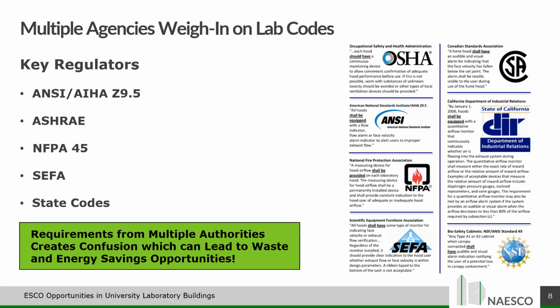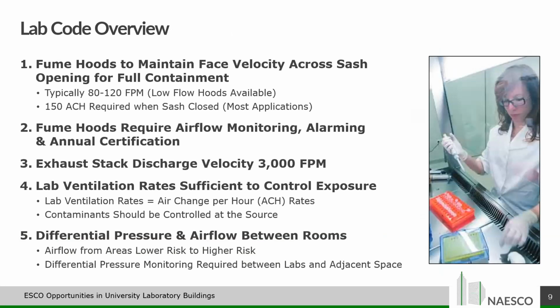But when you really dive in, there's about 5 or 6 different things with the code that I want to summarize for you, to give you a good feel for what's really important to pay attention to when you're retrofitting labs. First, it's about the fume hood. The fume hood is the most critical piece of equipment in a lab. That fume hood needs to be functioning properly all the time, or else you're putting the lab users at risk. And you need to maintain a face velocity across the sash opening at all times between a range, generally 80 and 120 feet per minute.